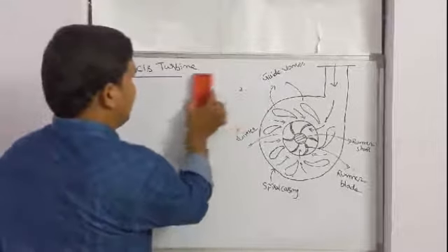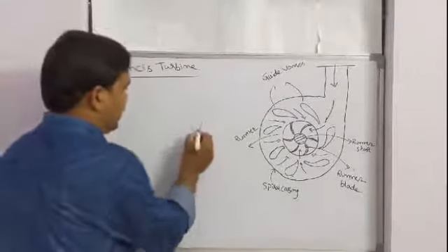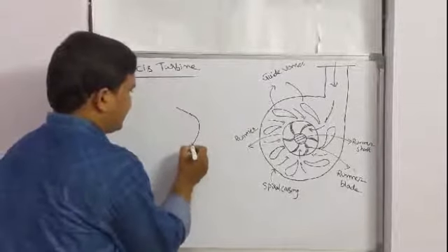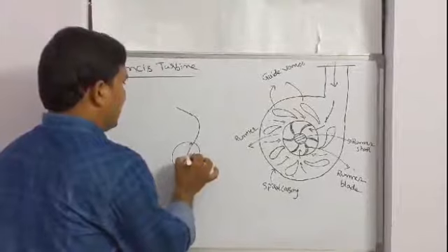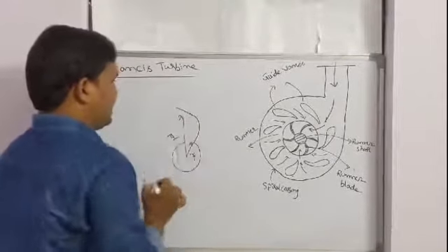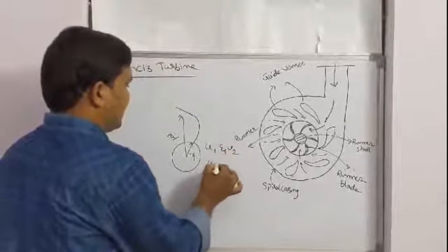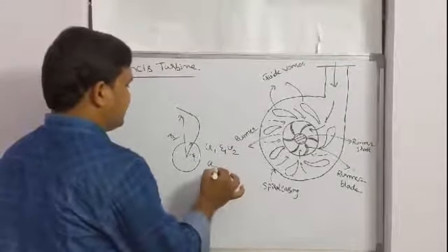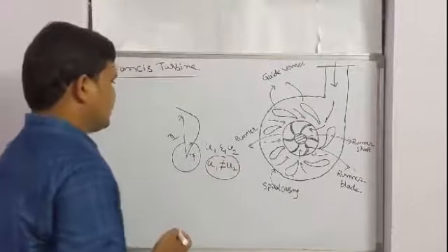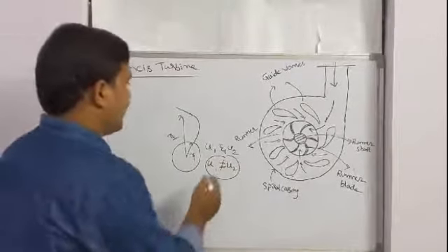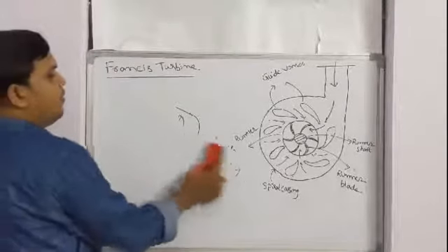as in a Francis turbine, the water enters at one radius and leaves at another radius. This means whenever R1 and R2 vary, then U1 and U2 also vary. Therefore in a radial flow turbine and a Francis turbine, U1 is not equal to U2. So please remember, U1 is not equal to U2 in a Francis as well as a radial flow turbine.